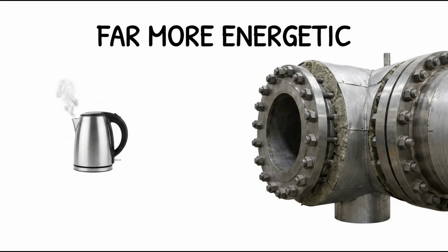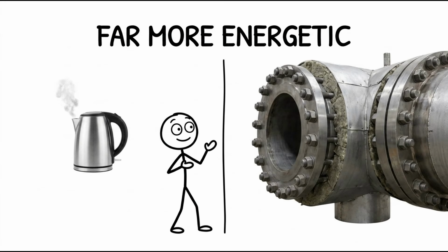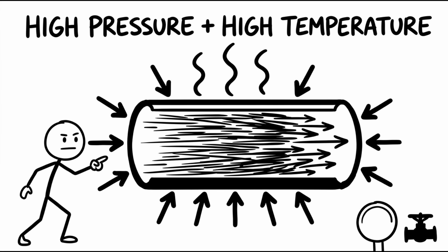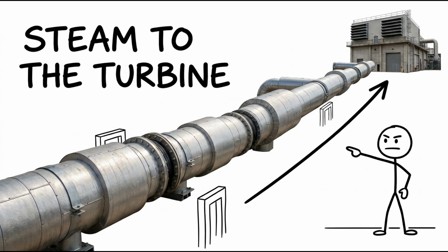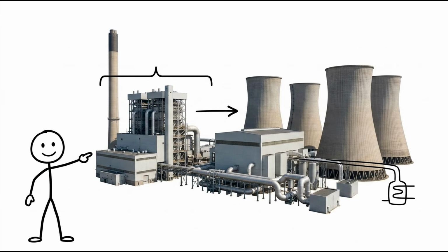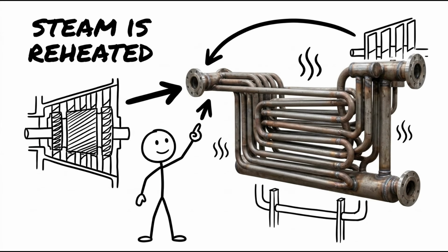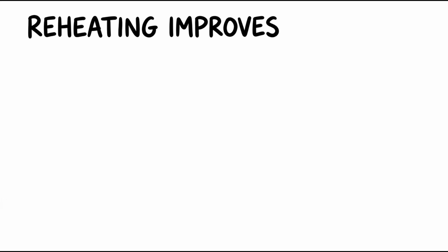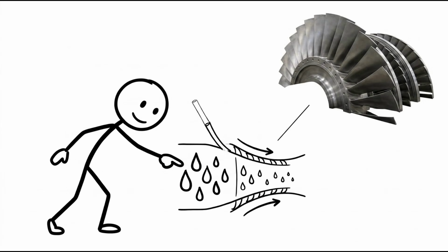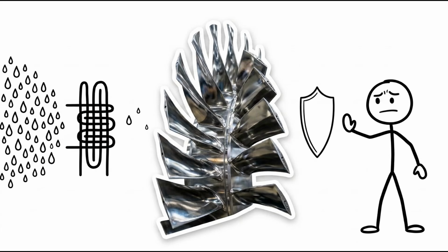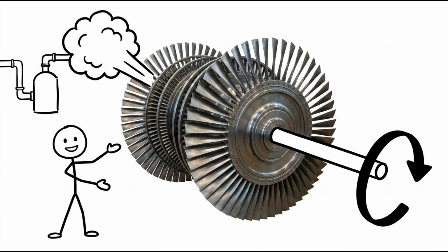As water absorbs heat inside the boiler, it changes into steam, but the steam leaving the boiler is far more energetic than the steam produced by a household kettle. It is created at extremely high pressure and temperature and is directed through large, heavily insulated pipes toward the turbine building. In many steam power plants, additional heating systems raise the temperature of the steam after its first expansion. This reheating process improves efficiency and reduces moisture inside the later stages of the turbine, protecting the turbine blades from excessive wear. The turbine is where thermal energy begins its transformation into mechanical energy.